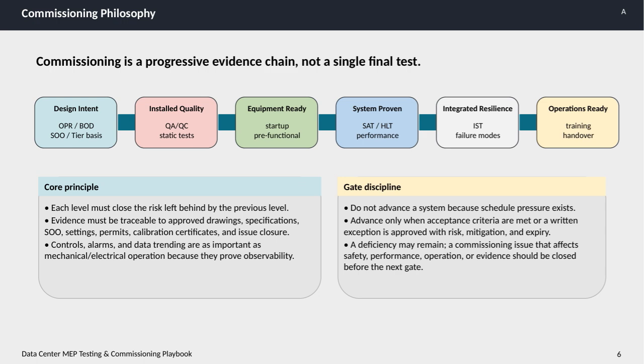Next, we ensure the equipment is ready through pre-functional startup activities. Once that's confirmed, we perform system-level testing with site acceptance tests and heat load tests to prove performance. We also include integrated system testing, which focuses on failure modes to confirm system resilience. Finally, we make sure the system is operations ready by conducting thorough training and completing a formal handover. A core principle here is that each stage must address and close out any risks or issues left from the previous phase. All evidence must be traceable back to approved documentation, from drawings and permits to calibration certificates and issue closures. Controls, alarms, and data trending are just as crucial as mechanical and electrical operations because they demonstrate observability.